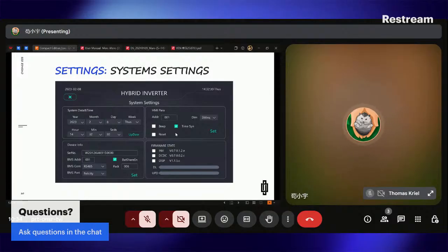And the second step is we need to let the inverter get into the standby mode. That means we need to turn off the PV and the battery button. So we need to turn off 2 buttons on the inverter, then it will go to standby mode. And we can let the customer go back to the main page, click on the inverter icon and take a picture so that we can make sure it's at the standby mode. Then we can remotely upgrade the firmware and fix the problem.